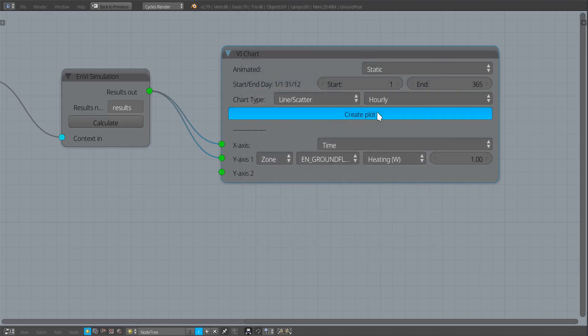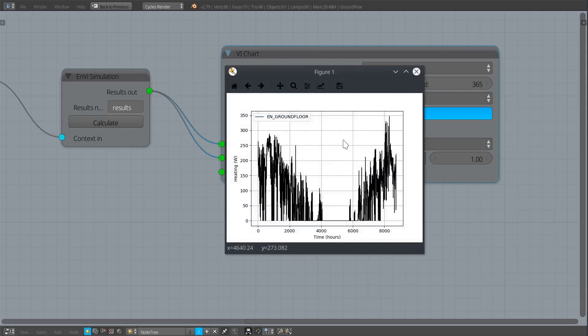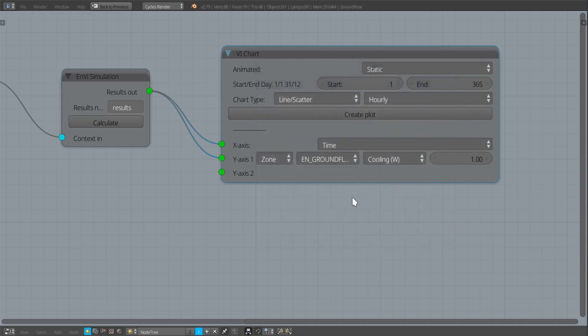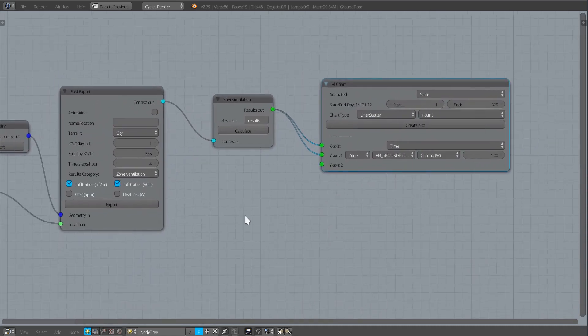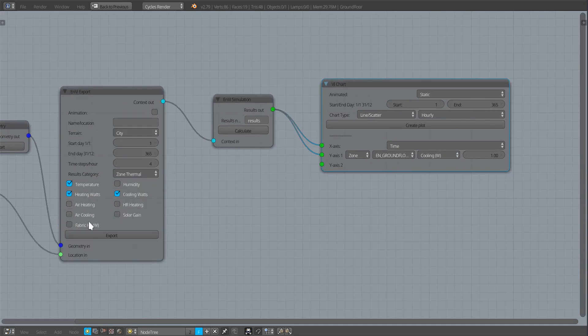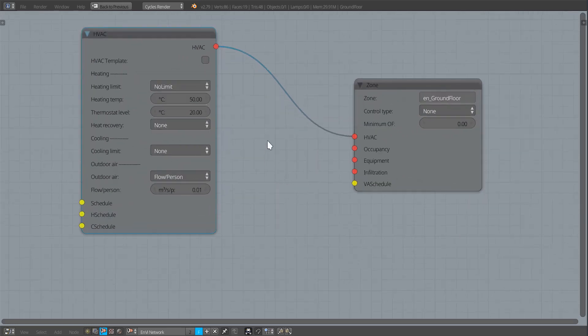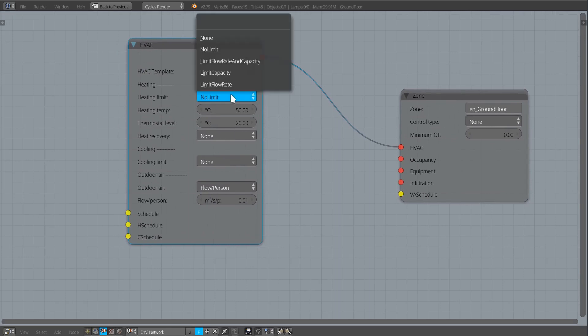Looking at heating watts, it's highest in winter, peaking at around 350 watts — not very much because there's no ventilation and it's a relatively well-insulated room — then becomes zero in summer when we don't need additional heat to keep the zone at 20°C or above. Cooling watts are zero since I haven't specified any cooling yet. To get these extra options appearing, make sure you select heating watts, cooling watts, etc. in your EnVi export node.